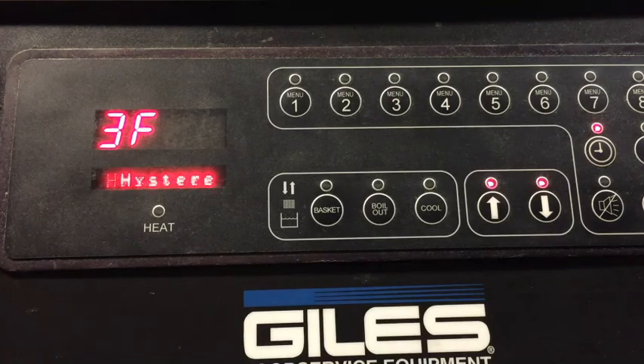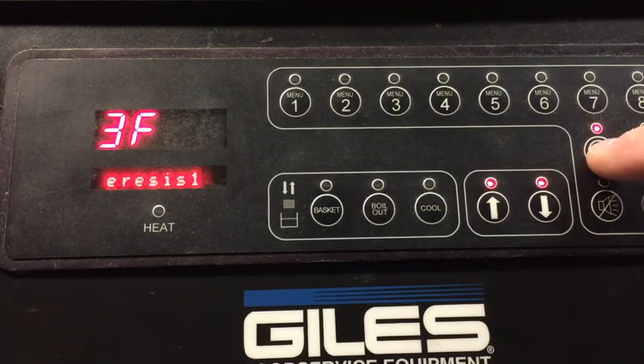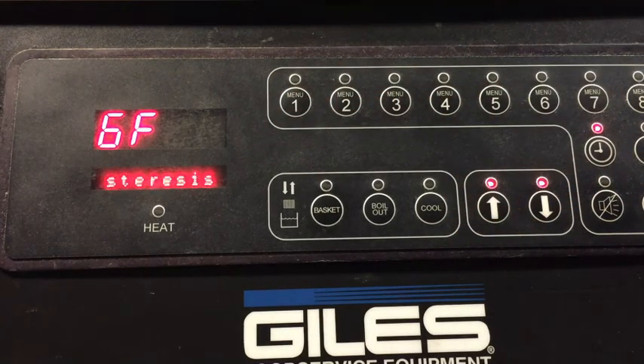The hysteresis. What the hysteresis is, say our set point is 350 degrees, when it gets 3 degrees below that, 347, when it starts to bump over to 346, that 3 degrees is when it's going to kick the heat back on. It's going to heat to that 350, it's going to shut the heat off, and then when it cools back down to 347 to 346, it'll kick it back on and bring it back up. So that's what that hysteresis is. You've got a hysteresis 2, and that's only for the gas machines. The big GGF 720s have a dual gas valve. The 3F would be for the first gas valve, and then if the temperature continued to fall, the other gas valve comes on to bring that temperature back up, and that's where the 6F comes in.